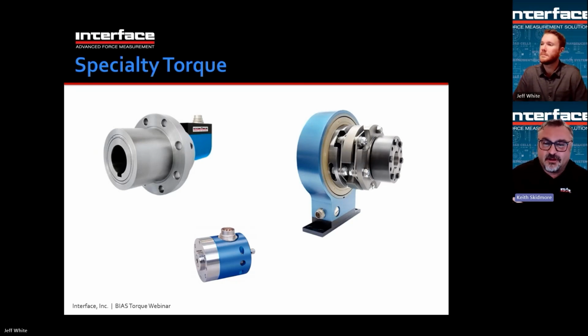Here we're showing some specialty torque sensors. There are a number of products in the market that are very specific to certain applications. On the upper left, there is a pulley torque transducer that actually mounts on a motor shaft, and the pulley mounts to the torque sensor. Typically, if you were to try to mount, say, a pulley on a torque sensor, the pulley tension or the belt tension would ruin the torque sensor. So a pulley torque sensor is a special device that allows the pulley to be mounted to it and can take the very high tension loads of the belt without damage.